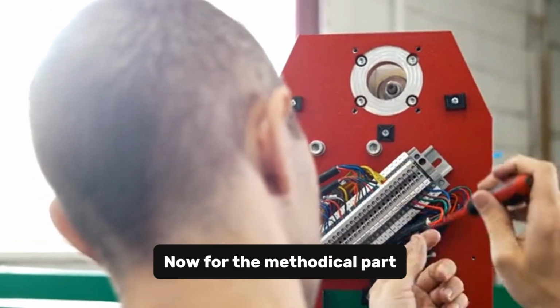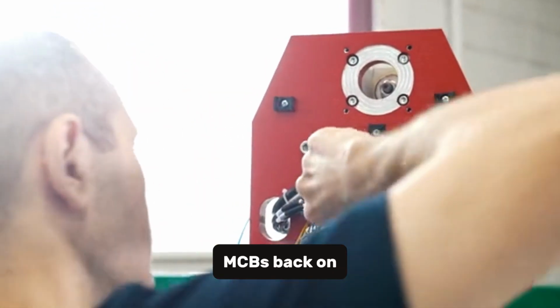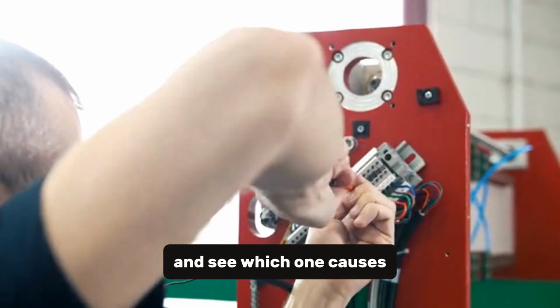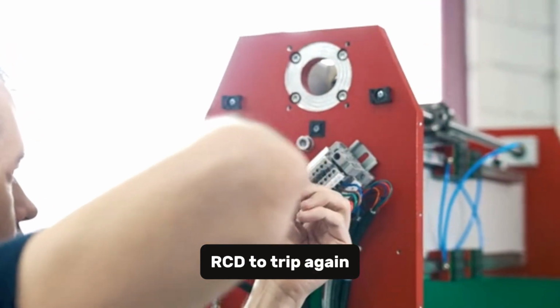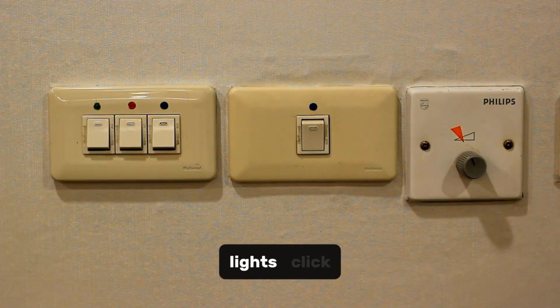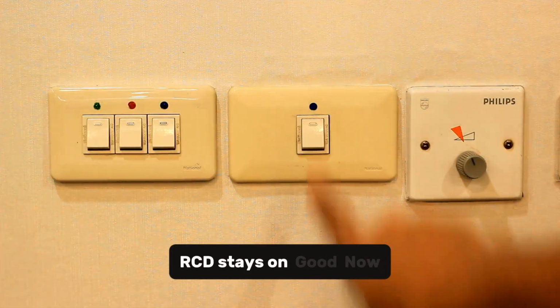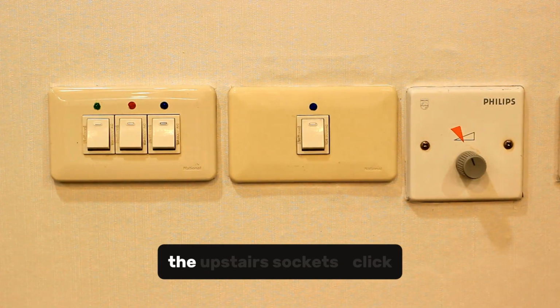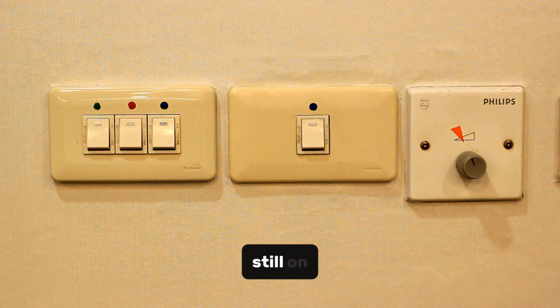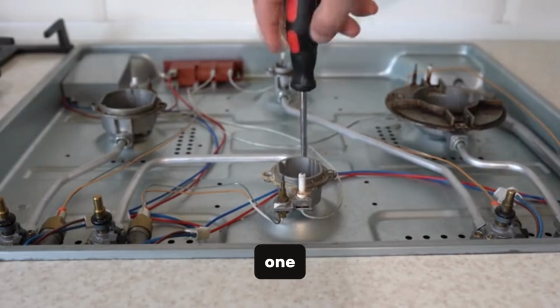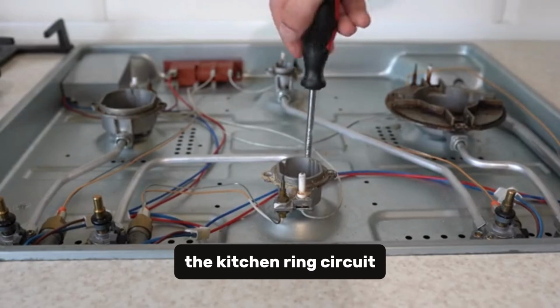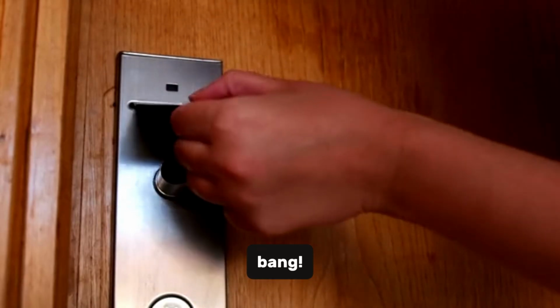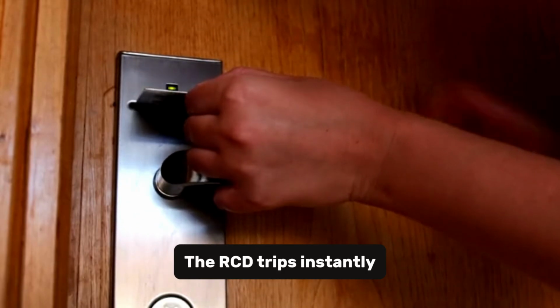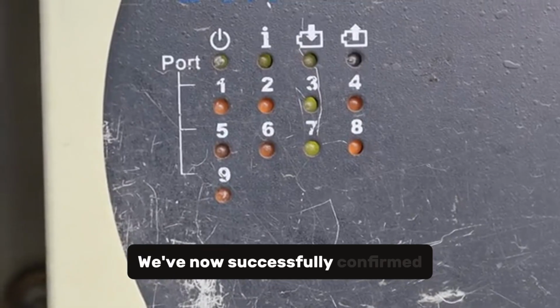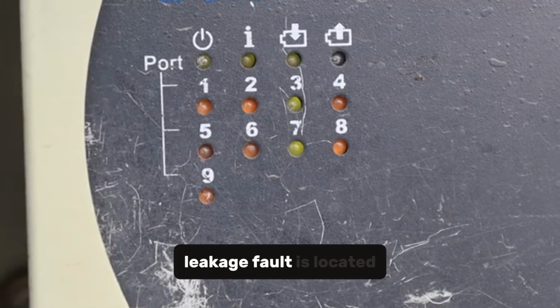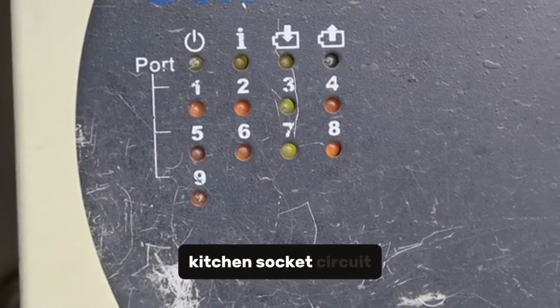Now for the methodical part. I'm going to switch the MCBs back on, one by one, and see which one causes the RCD to trip again. Let's start with the upstairs lights. Click. RCD stays on. Good. Now the upstairs sockets. Click. Still on. Okay, now for the big one. The kitchen ring circuit. I flick the switch, and bang. The RCD trips instantly. That's our culprit. We've now successfully confirmed that the earth leakage fault is located somewhere on the kitchen socket circuit.